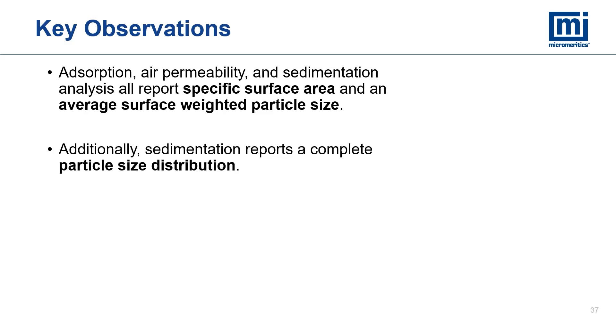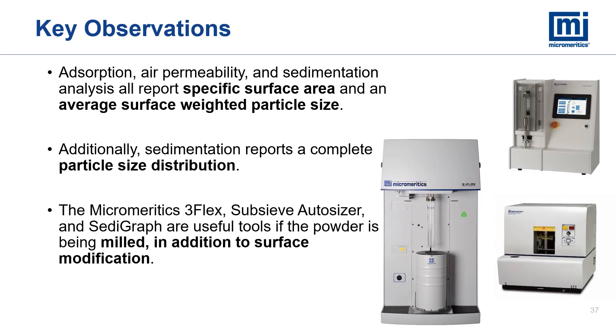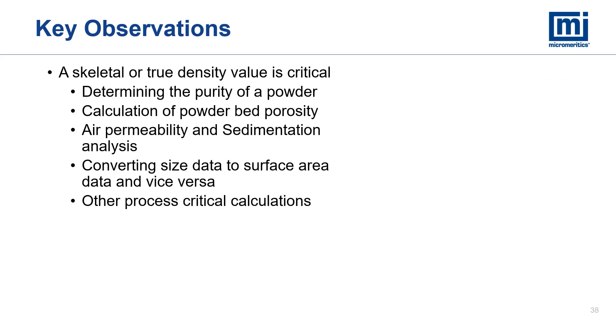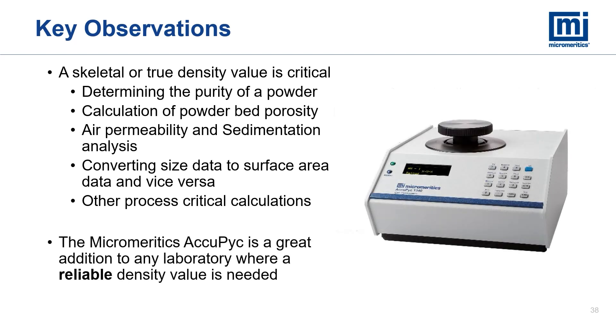Adsorption, air permeability, and sedimentation analysis all report specific surface area and an average surface-weighted particle size. Additionally, sedimentation reports a complete particle size distribution. The Micromeritics 3Flex, Sub-Sieve Autosizer, and Sedigraph are useful tools if the powder is being milled in addition to surface modification. Reviewing all the values calculated by the various techniques, one value stands out as probably the most critical: all the data used a skeletal density value to make appropriate calculations. The skeletal or true density helps to determine powder purity, calculate powder bed porosity, perform air permeability and sedimentation analysis, convert size data to surface area data and vice versa, and other process-critical calculations. The Micromeritics AccuPyc is a great addition to any laboratory where a reliable density value is needed.